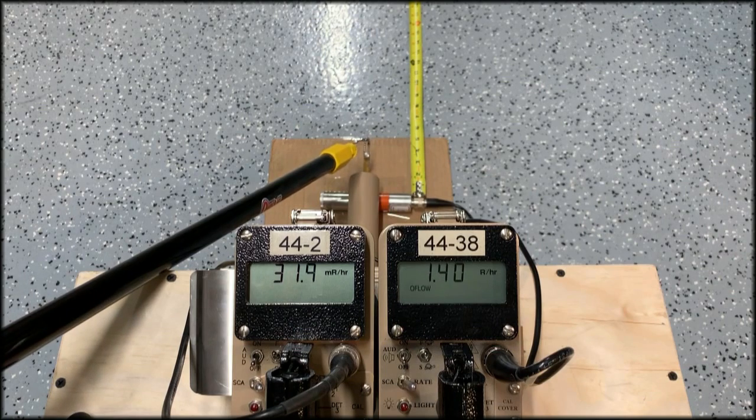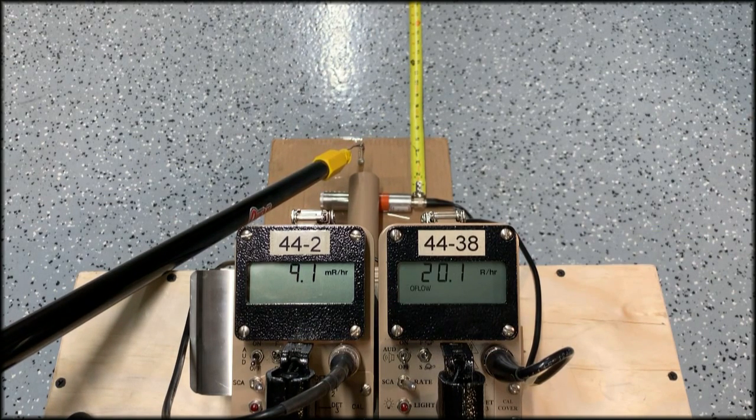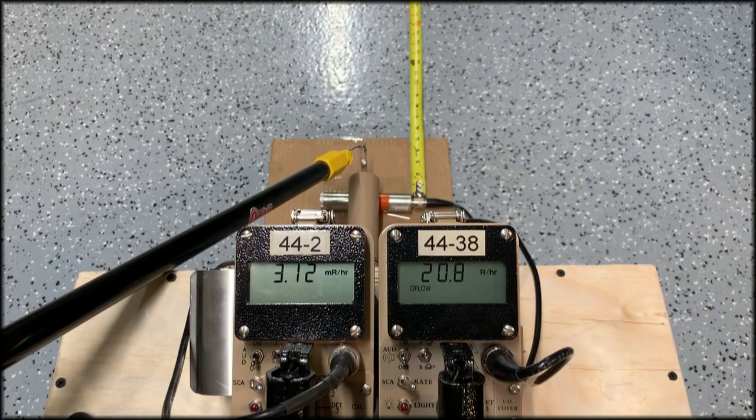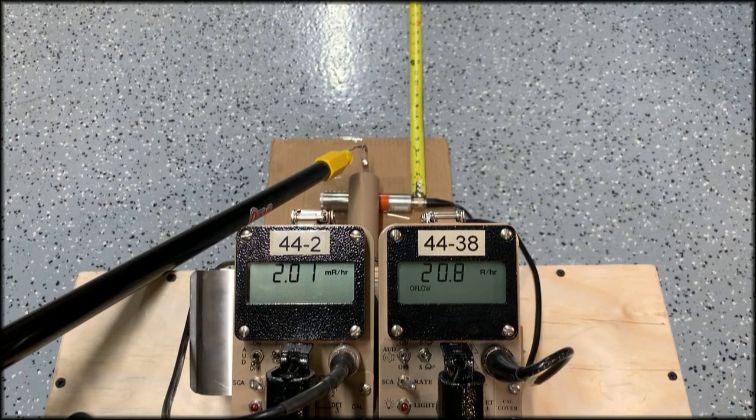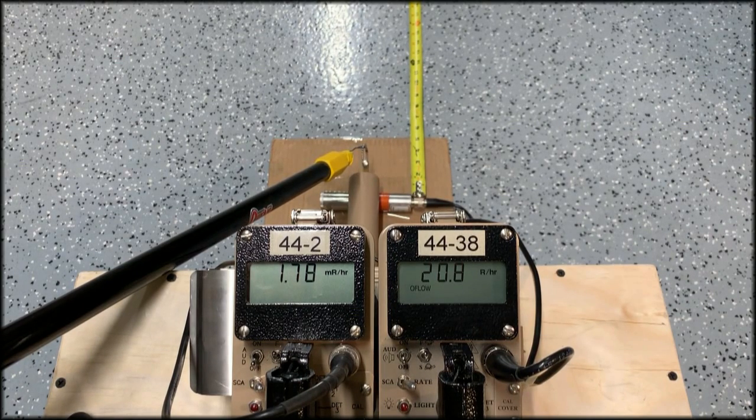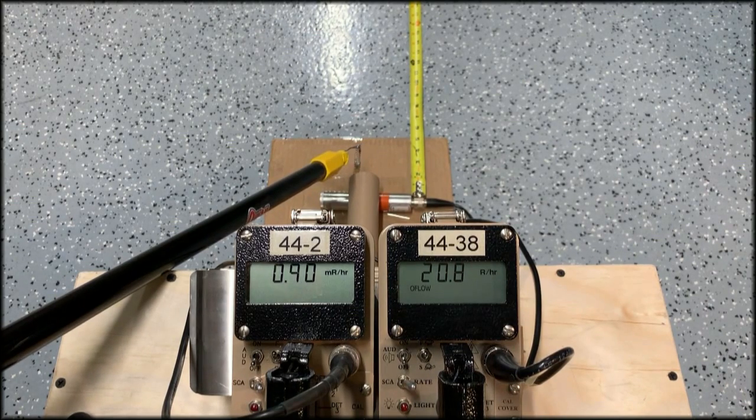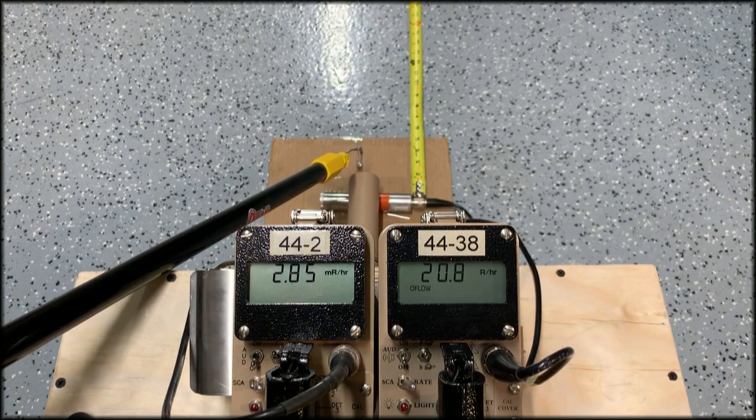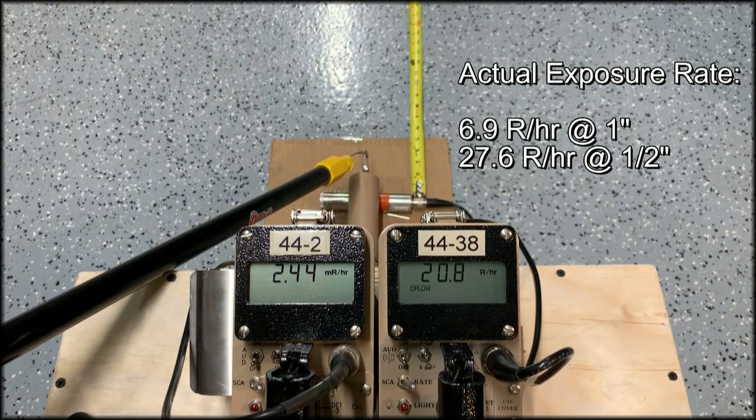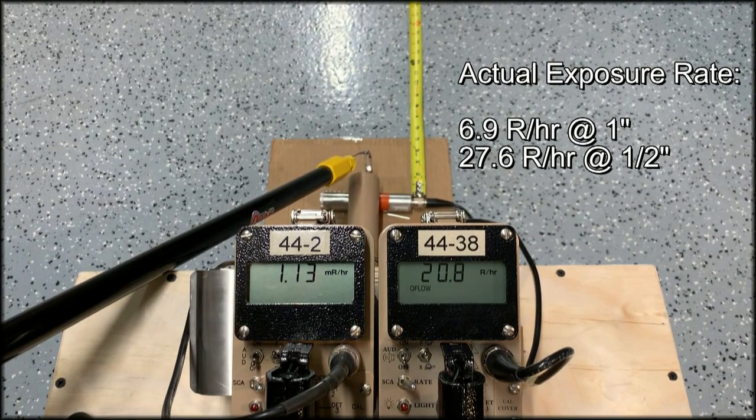And as I come in even closer, and I get right up close, maybe an inch or so away from that 44-2, you can see it's telling me it's only 2 mR per hour. But I'm, what does it say, 20 R per hour on the other detectors. So obviously this is a real problem.